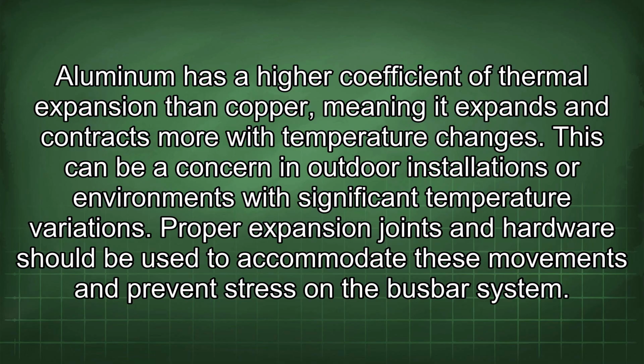Aluminum has a higher coefficient of thermal expansion than copper, meaning it expands and contracts more with temperature changes. This can be a concern in outdoor installations or environments with significant temperature variation. Proper expansion joints and hardware should be used to accommodate these movements and prevent stress on the busbar system.